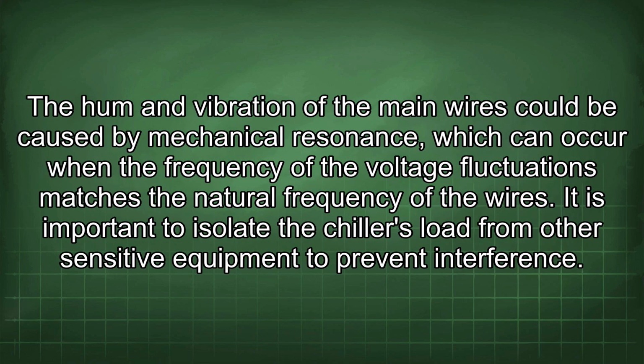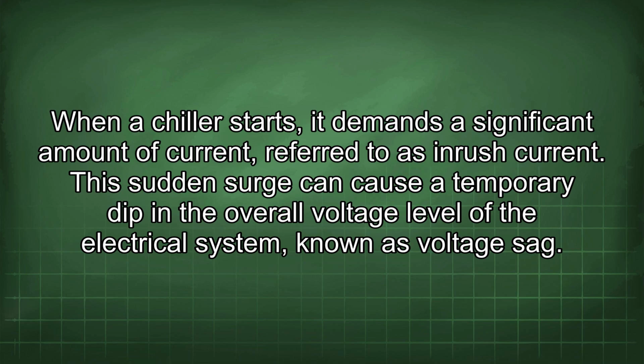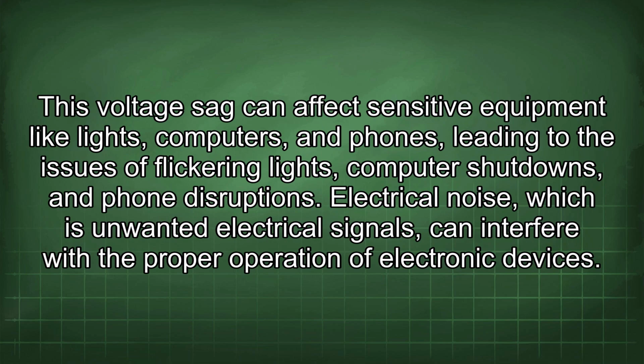The hum and vibration of the main wires could be caused by mechanical resonance, which can occur when the frequency of the voltage fluctuations matches the natural frequency of the wires. It is important to isolate the chiller's load from other sensitive equipment to prevent interference. When a chiller starts, it demands a significant amount of current, referred to as inrush current. This sudden surge can cause a temporary dip in the overall voltage level of the electrical system, known as voltage sag. This voltage sag can affect sensitive equipment like lights, computers, and phones, leading to the issues of flickering lights, computer shutdowns, and phone disruptions.